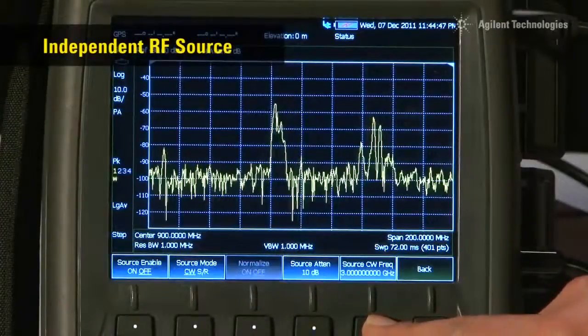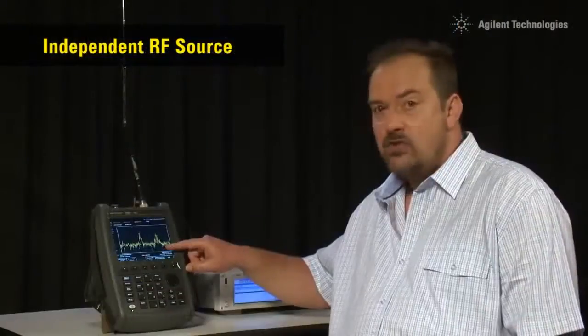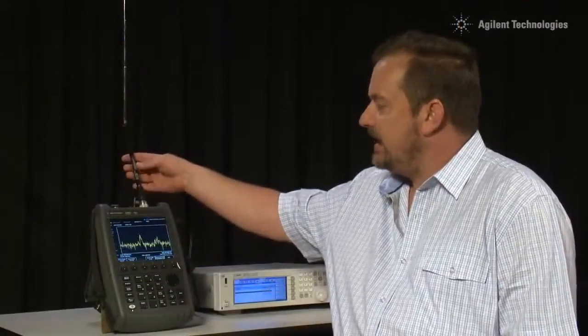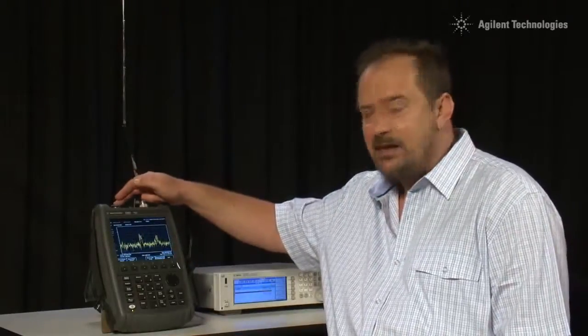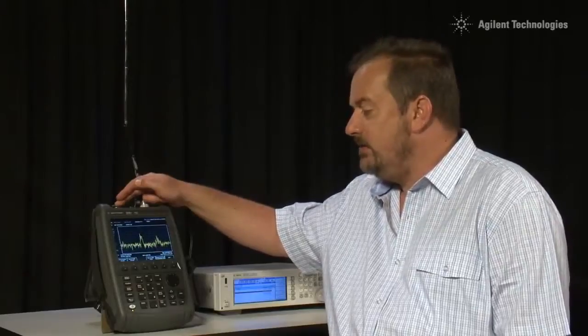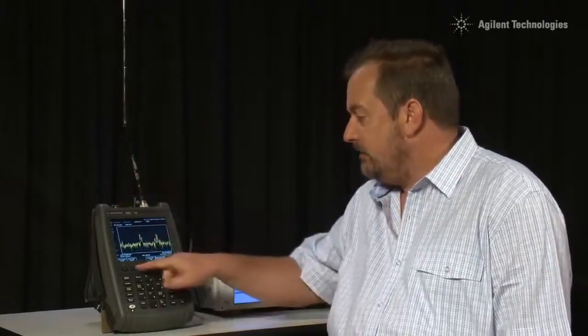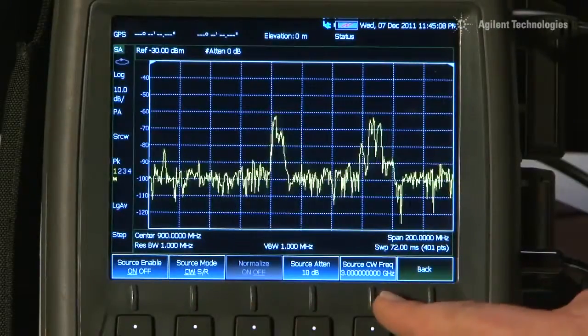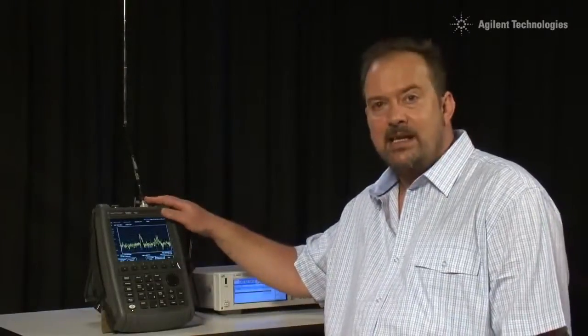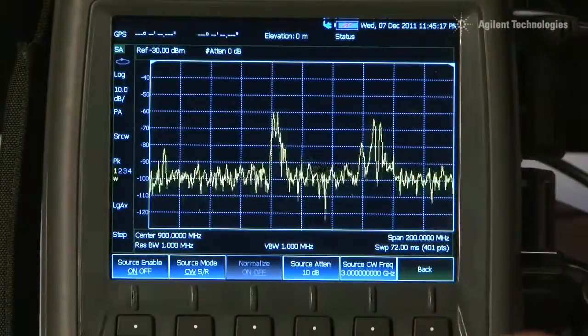One unique feature of the FieldFox is its independent source. Even though we are currently using the spectrum analyzer as a normal spectrum analyzer with, in this case, an antenna monitoring some frequencies coming off air, the signal generator within the FieldFox can be used totally independently. In this case, we have it turned on. It is being used as a CW source and the frequency can be set completely independently from whatever frequency the spectrum analyzer is set to. So we can use it as a source to perhaps test interference on a receiver or even use it as a mobile beacon.